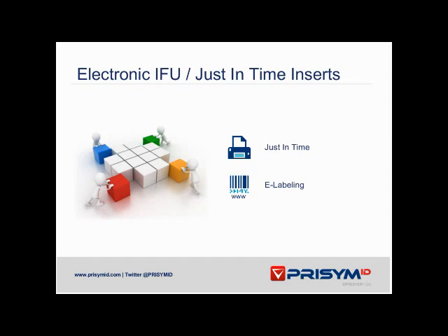It says, look, here's a general case, and the general case is that you must put a unique device identifier on everything. That's the general case. And now here's a list of exceptions, and it's those exceptions which make the complexity here. So the general case for a surgical set or a kit is that it's the set or kit itself that must be uniquely identified.